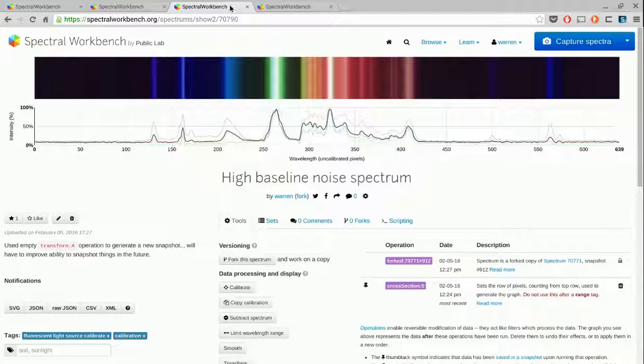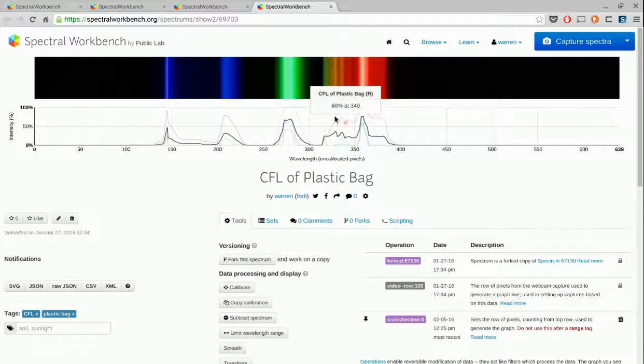You might get something that looks a little bit more like this. This is a bit blurred. It's not ideal, but it will work perfectly well. This is another example. You notice that the green channel is totally blown out here, but because we have good data in the other channels, we can still do this. You really do want to look for this sort of double green peak to get a good calibration. So what we do is we press calibrate.